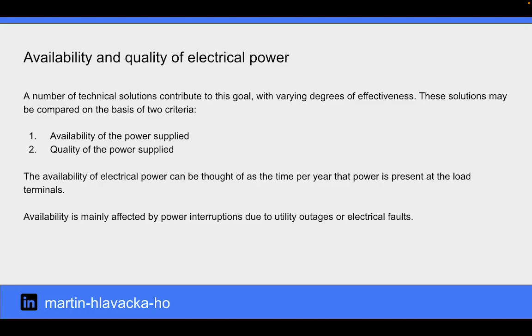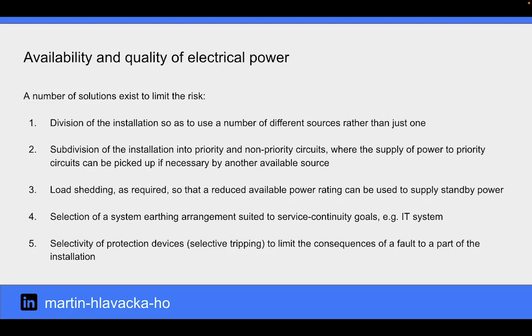The availability of electrical power can be thought of as the time per year that power is present at the load terminals. Availability is mainly affected by power interruptions due to utility outages or electrical faults. There are solutions to limit the risk: division of the installation to use several different sources rather than just one, subdivision of the installation into priority and non-priority circuits, where the supply of power to priority circuits can be picked up if necessary by another available source, load shedding as required so that a reduced available power rating can be used to supply standby power, selection of a system earthing arrangement suited to service continuity goals, for example IT system, and selectivity of protection devices to limit the consequences of a fault to a part of the installation.